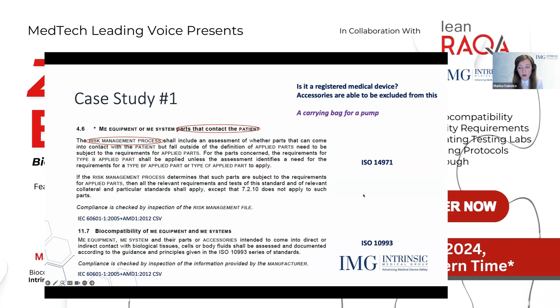So, talking about this example here, if we have a medical device, we have to perform a biological evaluation, even if it doesn't have any contact with the patient. We just need to document it. So we have to document that, okay, no contact with the patient. And surely follow ISO 14971 for risk management processes.